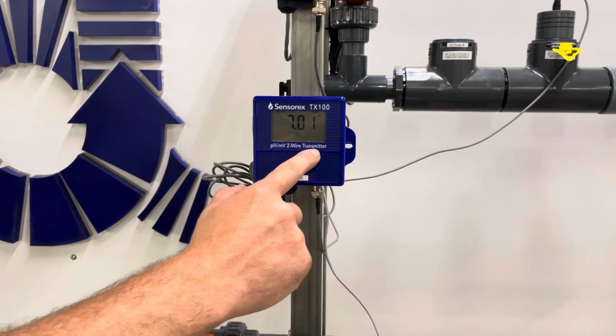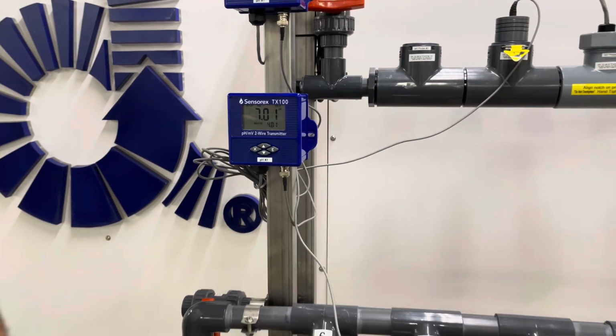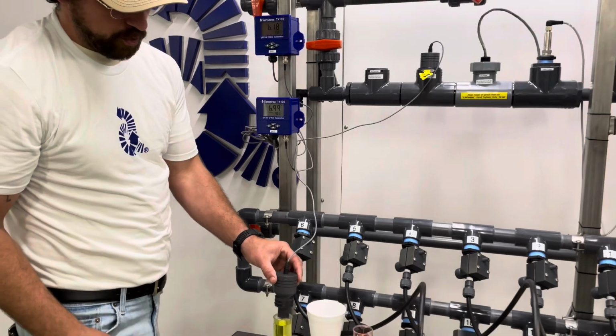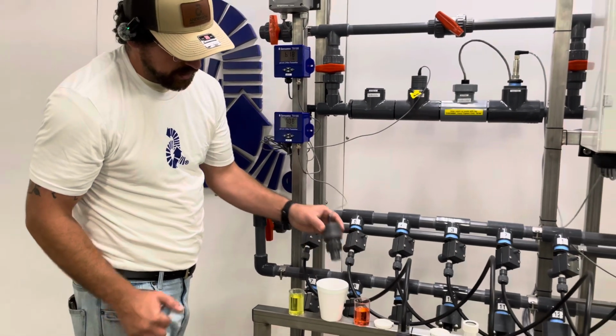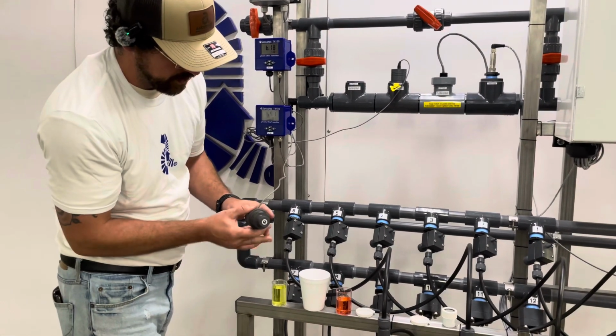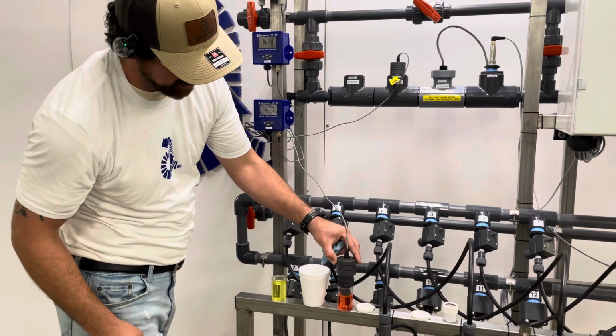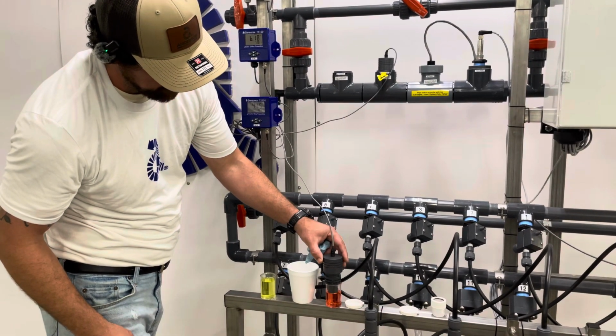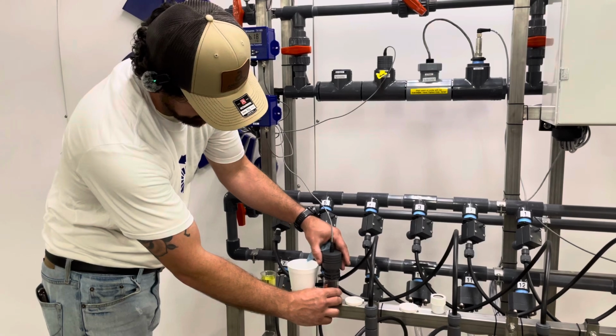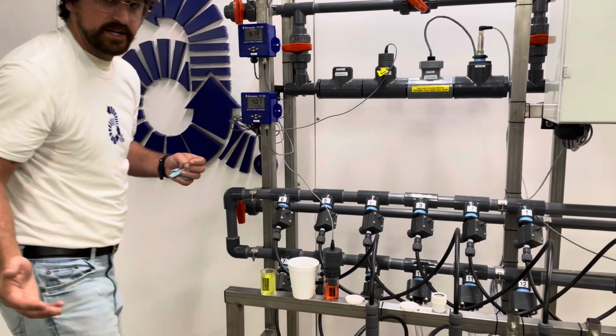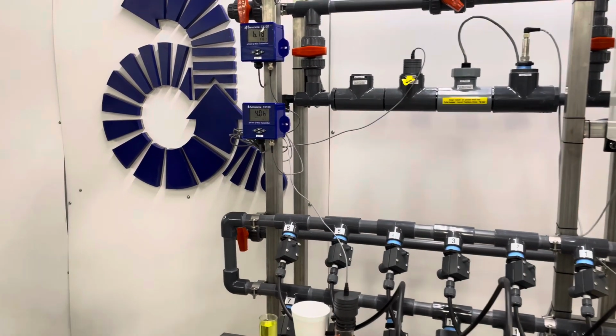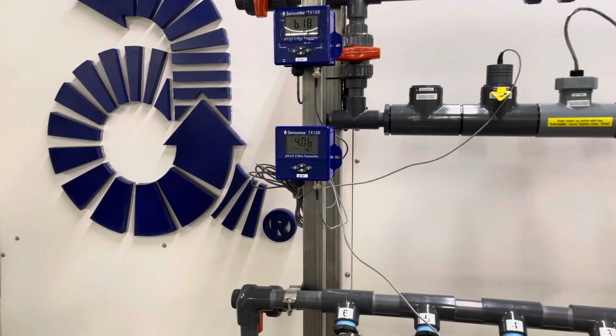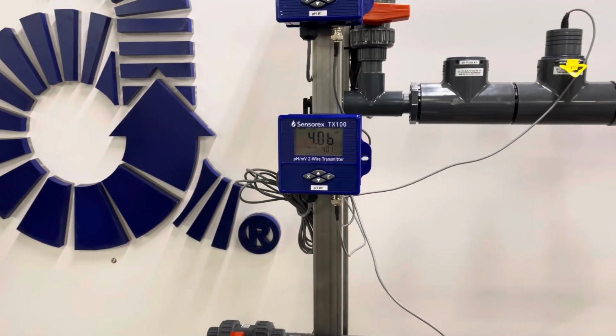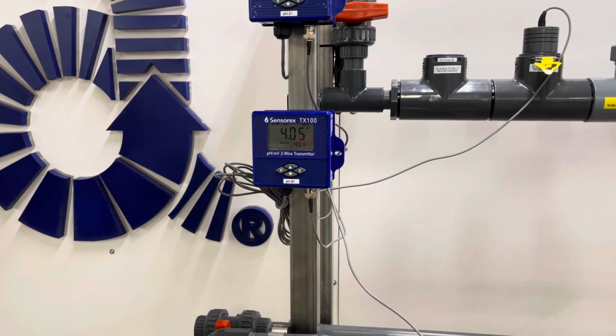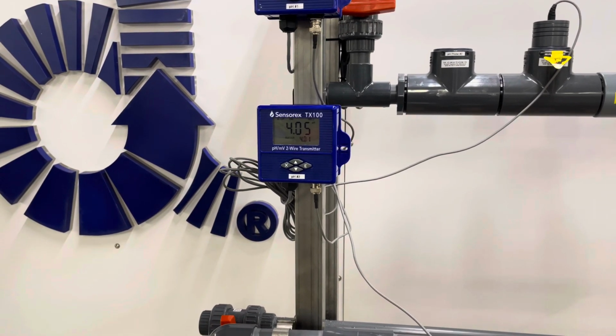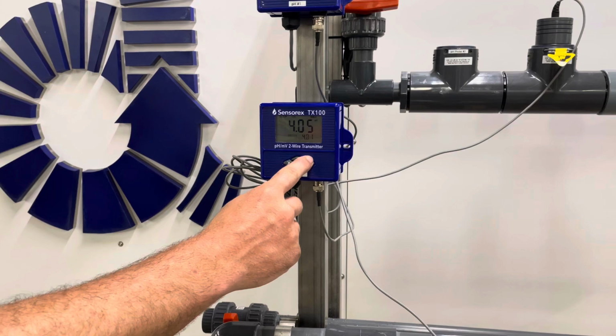And now it's blinking 4.01, telling you to put it in the 4 solution. So we'll take the pH probe out of 7, rinse it, then we'll shake dry. And we'll put it in 4, shake it around, make sure there's no air bubbles. And now we'll wait about another 45 seconds or until this top number stabilizes. And now that we've waited about 45 seconds, we'll press E to lock that in.